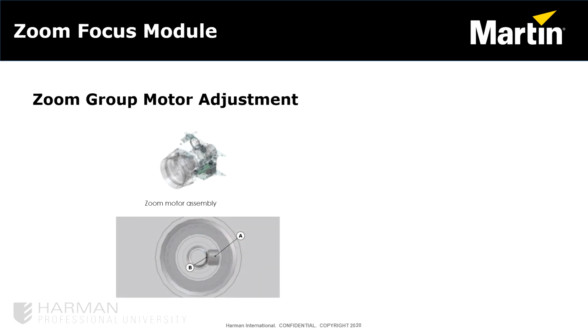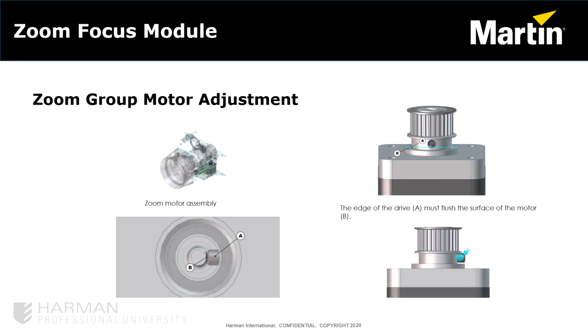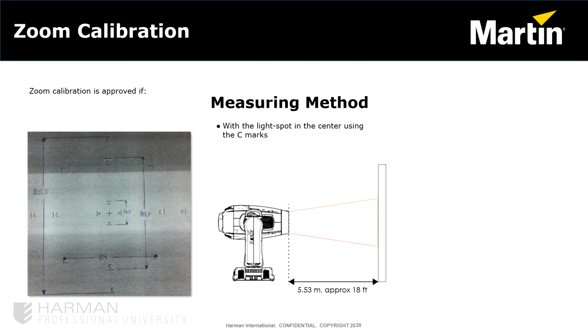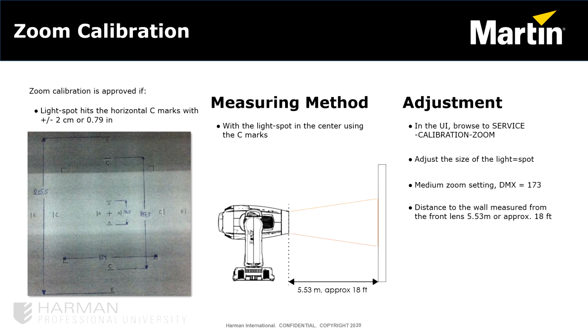The zoom group motor doesn't actually have an adjustment or a spacer. When referencing the images, take note that you need to make sure that the edge of the drive is flush with the surface of the motor. The zoom focus calibration is slightly different, as it requires the same calibration distances mentioned in the previous video. It is necessary to make a map that can be projected to, as shown in the left image. The measurements need to be written or printed showing the spacing. When performing the calibration, you can focus and zoom within those parameters.